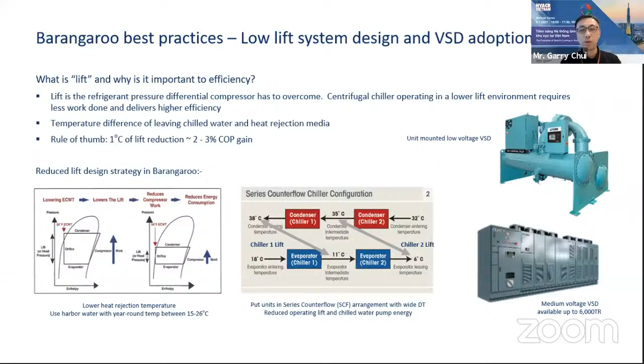Yeah. So traditionally, if you look at the left-hand side of the slide, the chillers are mostly arranged in a so-called parallel arrangement, putting the units side by side, and we have a so-called design condition for the selection of the equipment, so all the chillers in parallel follow the same set of conditions. For example, for chillers number 1 and 2 on the left-hand side in parallel arrangement, the lift these two chillers operate at is defined by two leaving temperatures: the chill water supply temperature from the evaporator, and the heat rejection medium leaving temperature. In this example, that is 35 and 7. So the difference is 28 degrees C, which symbolizes the lift these two units have to overcome.